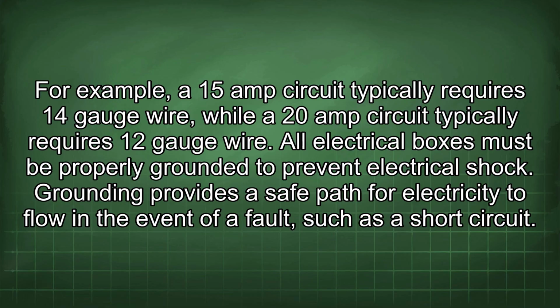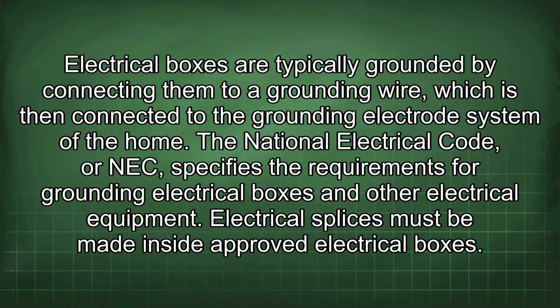All electrical boxes must be properly grounded to prevent electrical shock. Grounding provides a safe path for electricity to flow in the event of a fault, such as a short circuit. Electrical boxes are typically grounded by connecting them to a grounding wire, which is then connected to the grounding electrode system of the home. The National Electrical Code, or NEC, specifies the requirements for grounding electrical boxes and other electrical equipment.